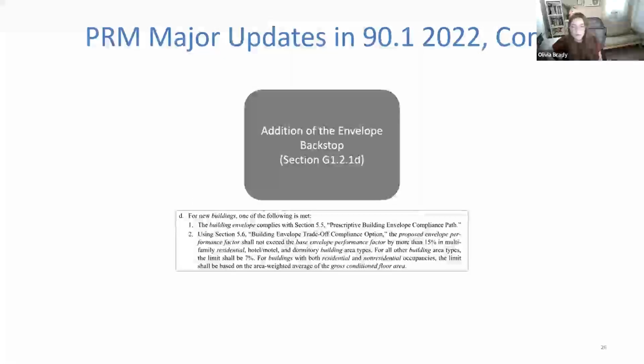All right, and then the last major update that I'll mention is the addition of the envelope backstop. And so I'm showing this excerpt from the standard on the slide. Projects need to either comply with all Section 5.5 prescriptive building envelope requirements, or they have the option of modeling the building using the building envelope trade-off compliance option. And the requirement for that is that the proposed envelope performance factor cannot exceed the base envelope performance factor by more than 15% for multifamily residential, hotel/motel, and dormitory buildings. And for all other buildings, the limit is 7%. And you would calculate a weighted average limit if you have a mixture of residential and non-residential occupancies.